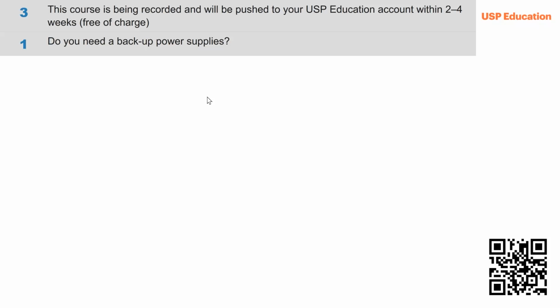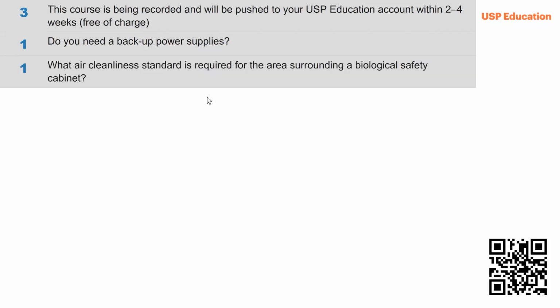No backup generator can start soon enough to make you feel good about the temperature in your incubator or in very small processes. A smaller process doesn't have the heat capacity. A great big block of ice stays a block of ice, but a tiny ice cube is gone as soon as the cold or heat hits it. So as part of your risk assessment, you're considering the heat capacity of the materials you're storing.